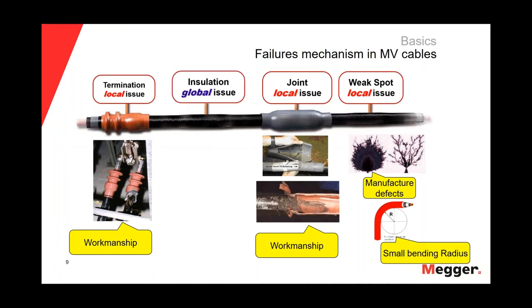On the other hand, we have global issues, which are related to the aging process of the insulation of our cables. They will be spread along all the cable — this is an aging condition of the insulation and will affect all the insulation of the cable. In the case of polymeric insulations, particularly XLPE insulation, the main reason for aging conditions is water tree degradation.